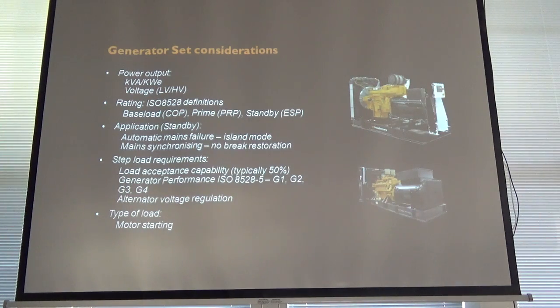Now often, on the data sheets, what you'll find is, let's pick a unit, 2 MVA prime, which is a Cummins QSK60G4 generator. Now that will use, a bit of an anorak I'm afraid, 396 litres per hour at 100% load. That's how much it uses when it's running at 100% load. But what you'll see is the fuel flow will actually be something like 680 litres per hour. So there's a flow and there's a consumption.